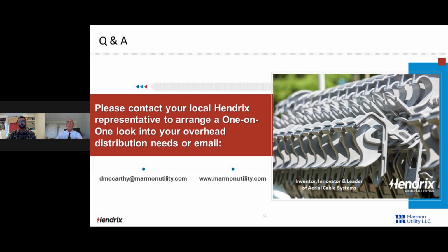But basically, you're using an armor rod to hold that conductor over maybe a 3-foot length. And then you're connecting that armor rod with an insulation piercing connector to the conductor itself. So there is no voltage potential difference across the insulation wall, which might otherwise cause PD or what have you. So we're basically putting everything at the same potential. But if somebody has more questions about tree wire versus spacer cable at 115 versus 69 kV, send those to me and I will answer them in excruciating detail with pictures, diagrams, and explanations.